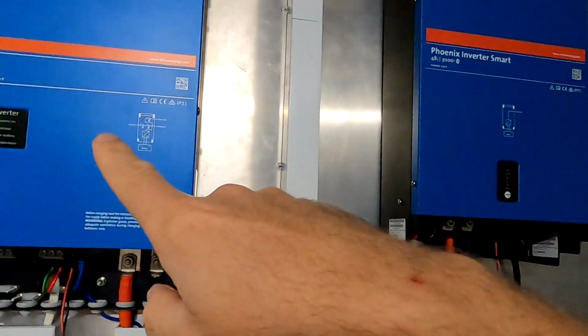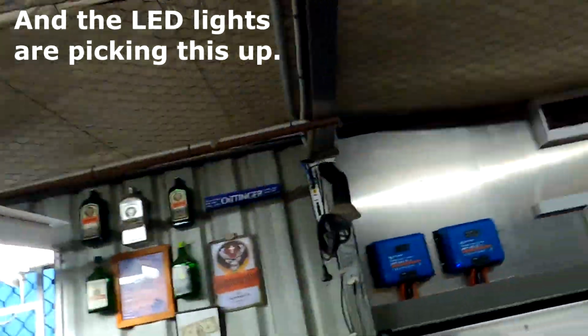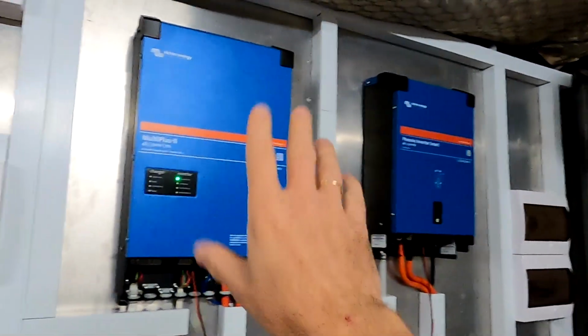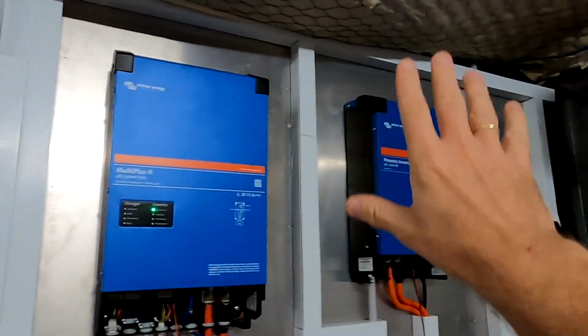Holy shit! Woo, yeah, this one is off, this one is on - that was the internal relay. And we could also see the lights flickering, because the changeover time is around 20 milliseconds for this device. So normally not critical for computers and other devices, but we could see the light flickering for a second when it actually happened. And now again the Multiplus is the only device and has turned off our generator.